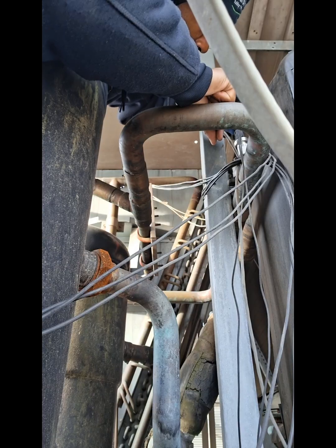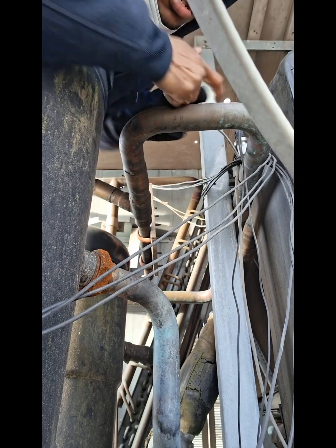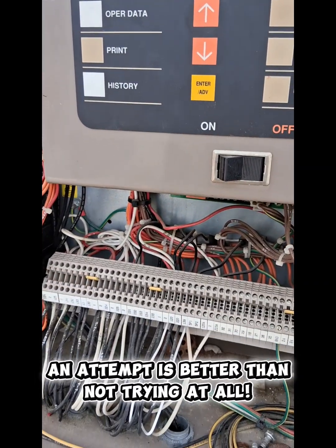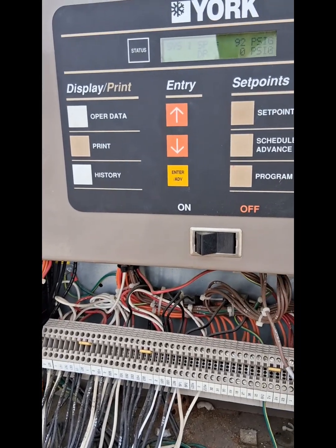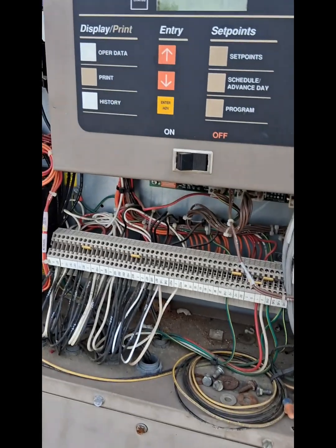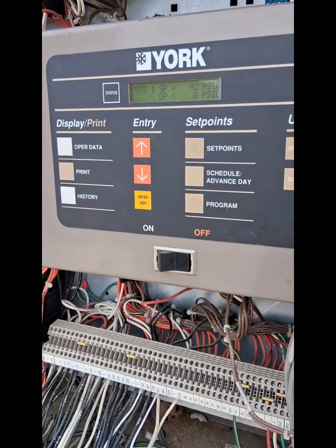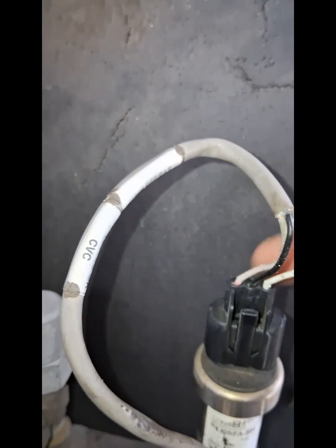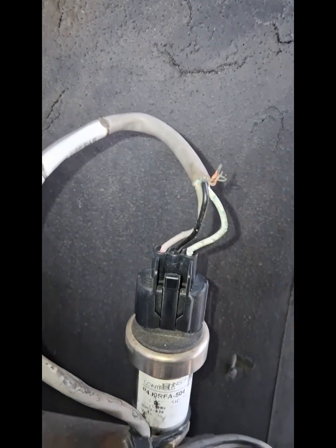Plug it in. Hopefully it'll work. Let's go try and see what the discharge pressure reading is now that I clipped it. I hope it's reading. Let's see. 0. Well, that's not good. Well, let's see. I'm gonna kill the power and turn it back on and see what happens. Well, I see the problem now that I look closer. That's the problem. So I'm gonna skin this back and try to fix it and see if I can get something going. I'll give you an update.